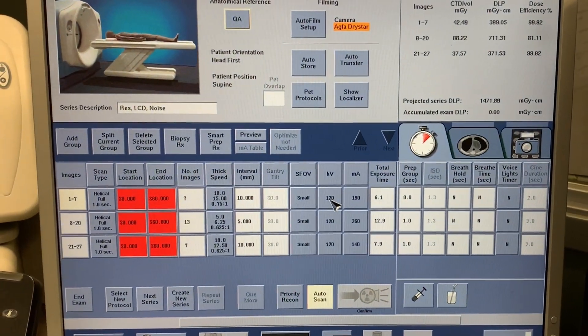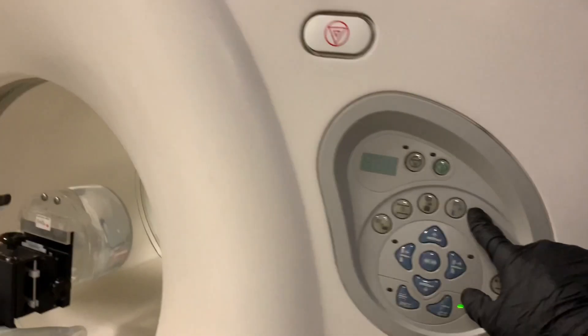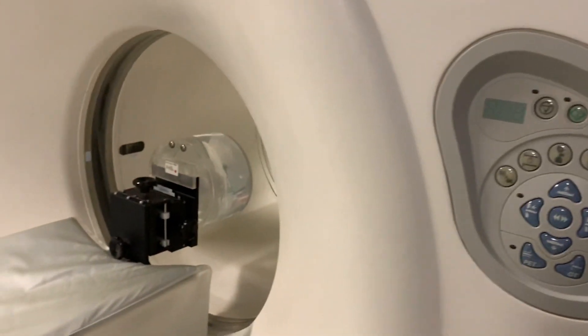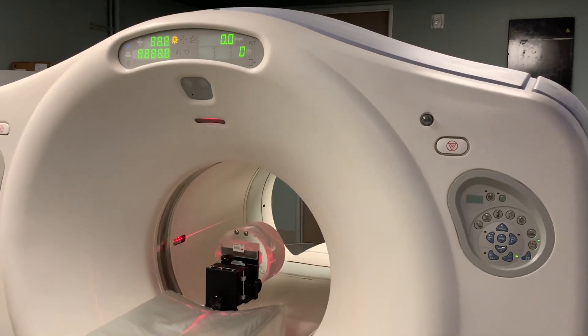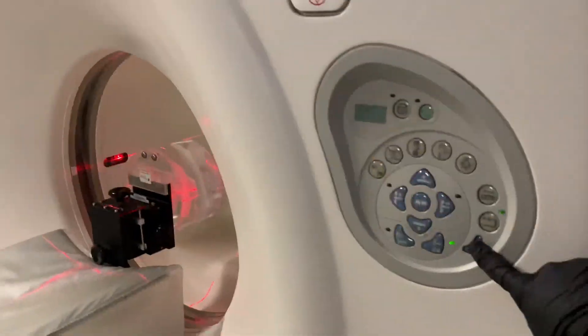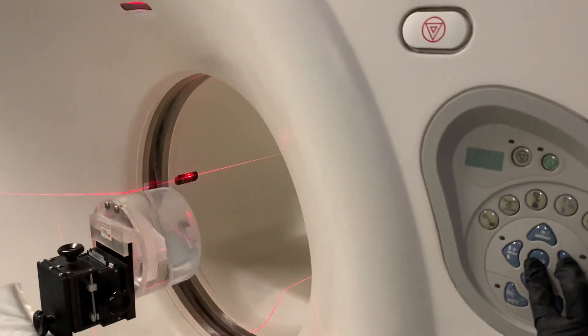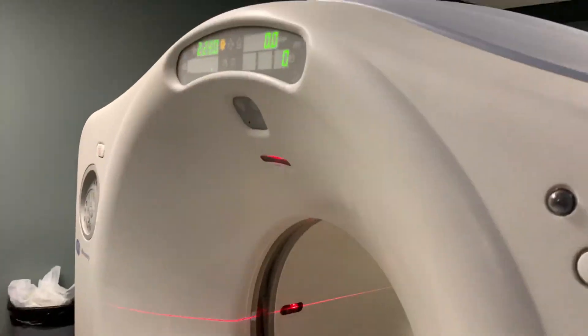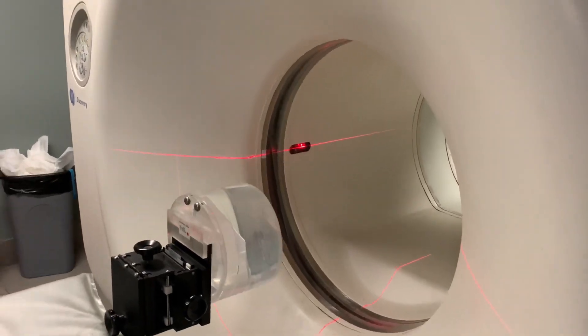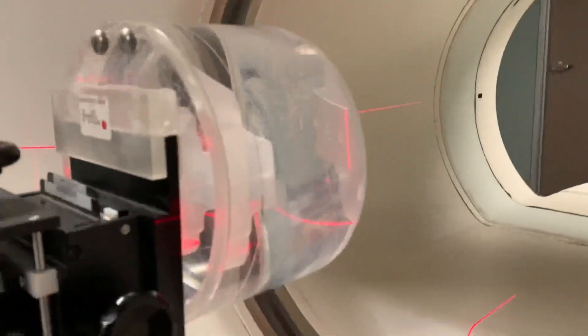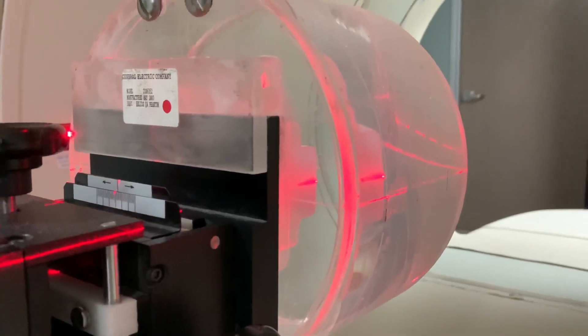To fix the error and resume CT scan operations, perform a landmark on the patient or phantom. Flashing eights along the top of the gantry indicate the table encoder is not synced with your CT system and may require additional steps. The link to that procedure can be found in the top right or down below in the description.